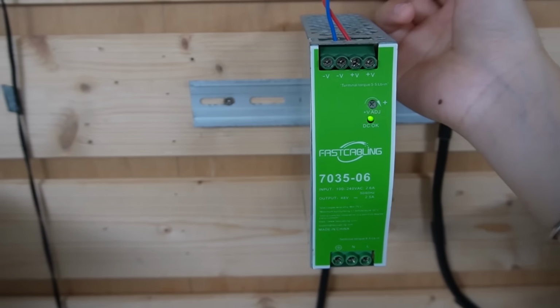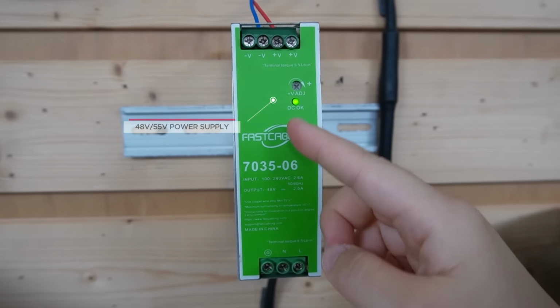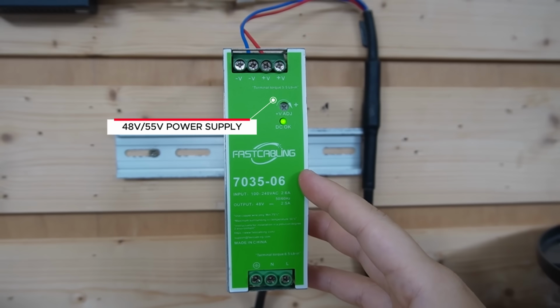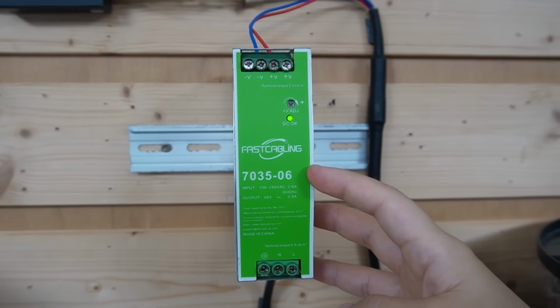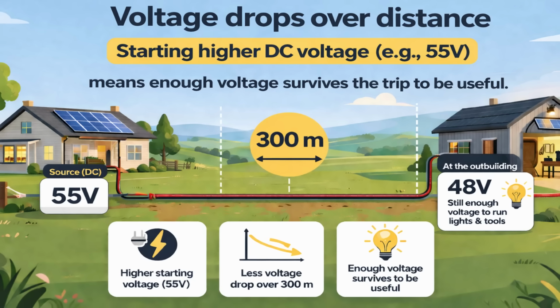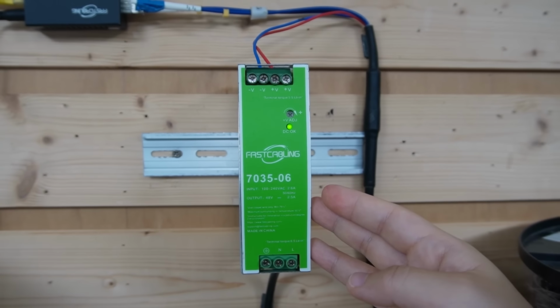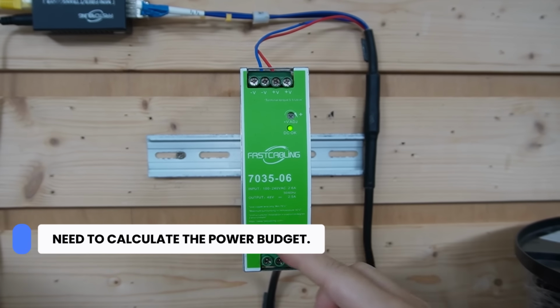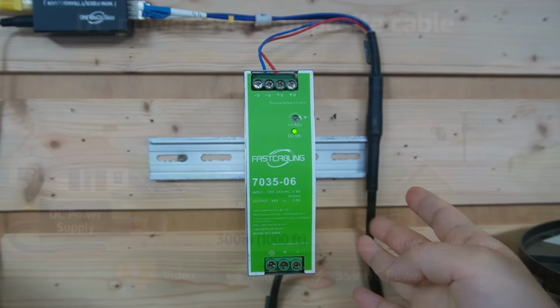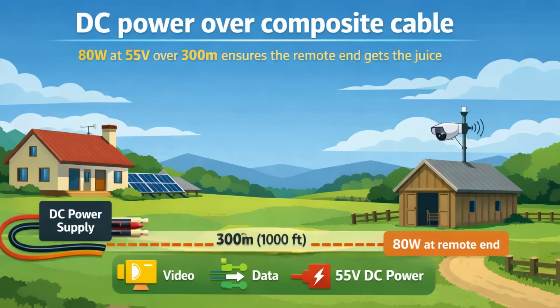We send a higher DC voltage, like 48 volt or even 55 volt, from the main building. Why? Physics. Over 300 meters voltage drops, so starting higher means there's enough voltage left to survive the trip and still be useful. We also have to calculate the power budget, for example setting 80 watts and 55 volts over 300 meters to ensure the remote end gets the juice.